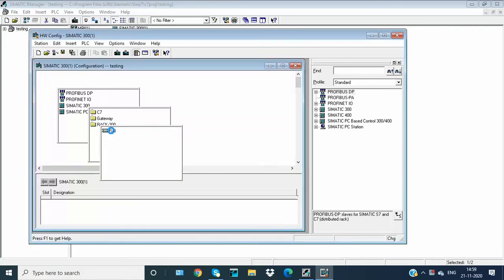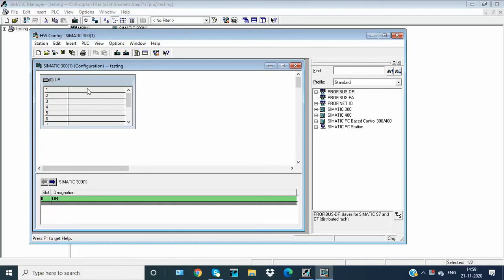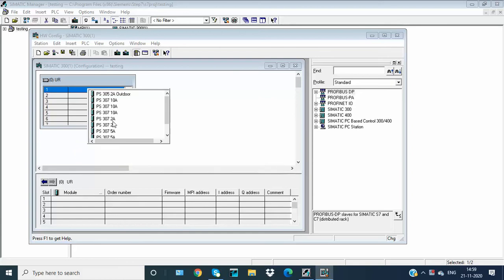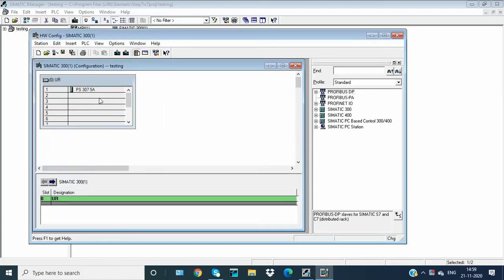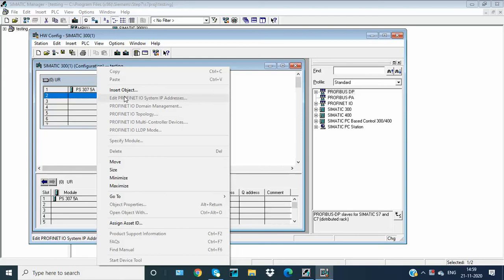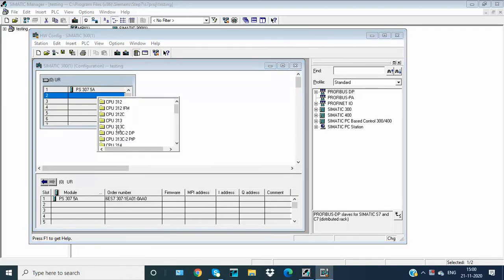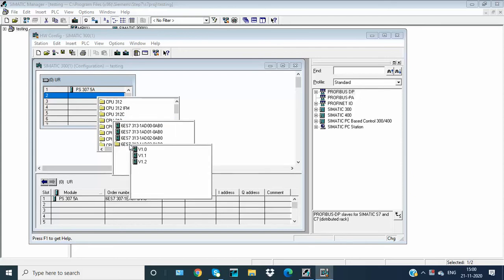Now on the first module we will use it as a power supply. I am using a power supply of 5 Ampere and CPU. The second slot is permanently for the CPU, and the first is for the power supply. I am using CPU 313 version 1.2.